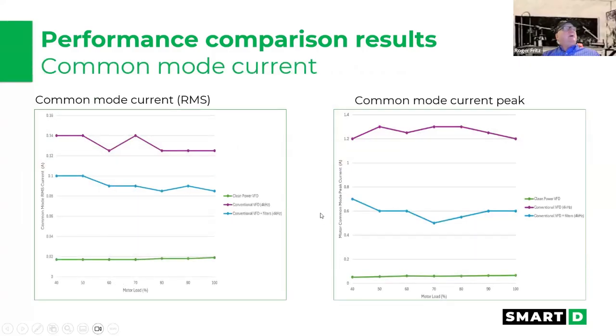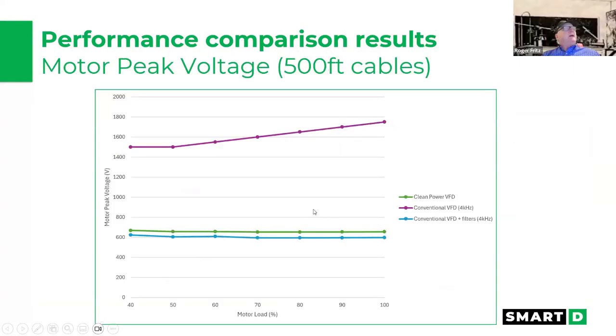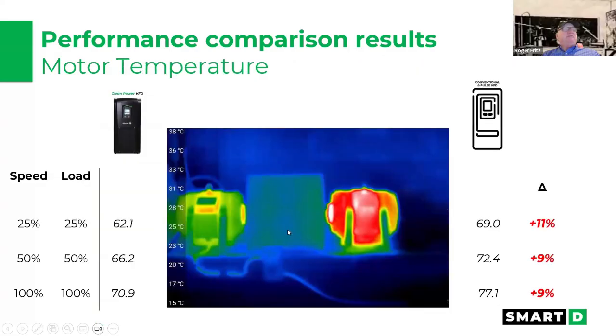So this is the peak load common mode voltage current comparison. This is also on a 500-foot cable, showing the actual peaking voltages that happen on a conventional VFD. If you do put a filter on, and that's at 4 kHz on a VFD, you get your conventional, and then you've got the clean power VFD. But you see also here that we don't have that voltage drop that you lose, which is additional energy lost from putting an output filter on. So every time you put a filter on, you lose a percentage of your power in both the input and output filters that are out there because that energy has to be used.